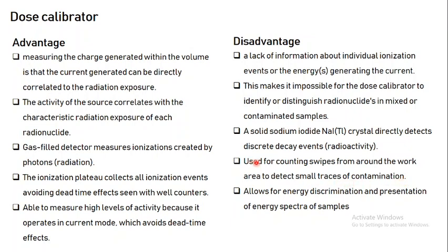Not only does it detect the sample actually held inside, but also any contaminating radioactivity present in the laboratory in the vicinity, detecting these radioisotope tracers. It allows for energy discrimination and presentation of energy spectra of a sample.